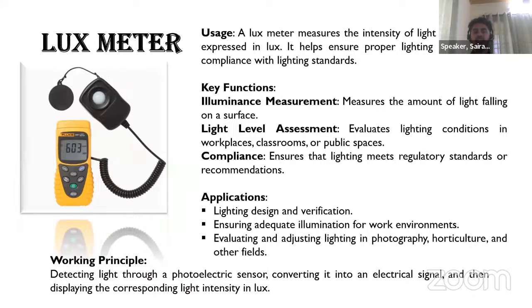Lux meter. This lux meter is used for measuring the illuminance generated by the light. We will have a set of standards as per building codes for the illuminance range for a conference room, for lecture rooms, or for hotels. We will be measuring it with the lux meter. If it is greater, then we will be optimizing the lights. If it is lesser than the level, then we will be suggesting they improve the lighting.